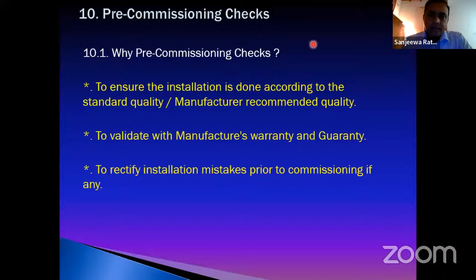Then pre-commission checks. The pre-commission checks are where we can minimize our errors in installation. So it is very important, because I think for a proper contractor it's a must to do a proper pre-commissioning checklist. The advantage of pre-commissioning is to ensure the installation is done according to the standard quality, or else the manufacturer recommended quality. If it is not done properly, the manufacturer's warranty will be nullified. The guarantees will be voided. And again, it is a chance to rectify installation mistakes prior to commissioning. So these are very important.